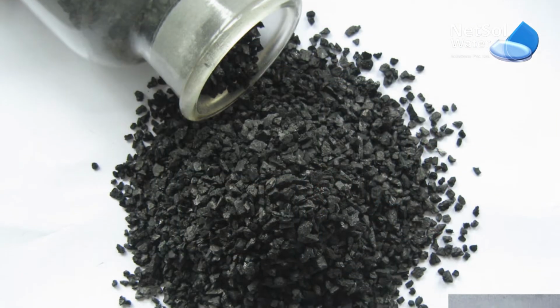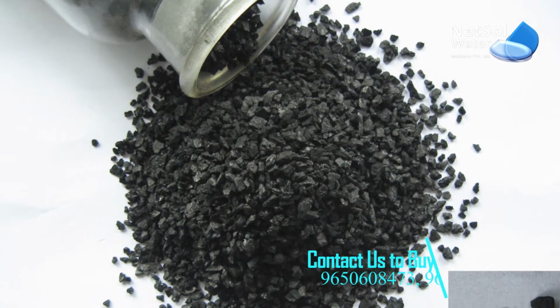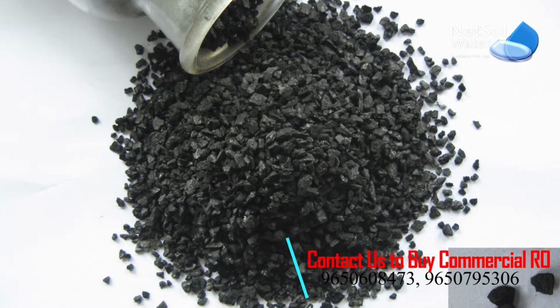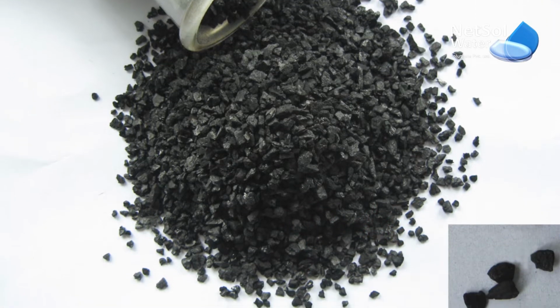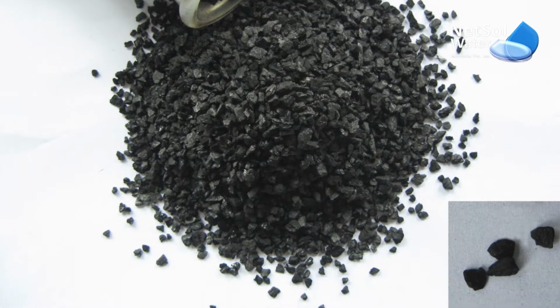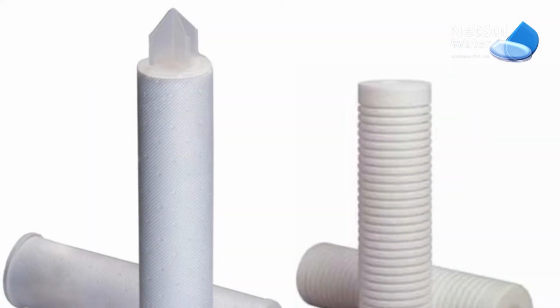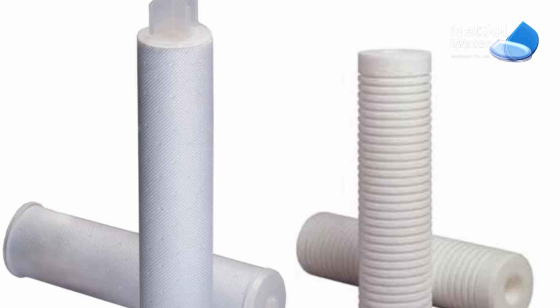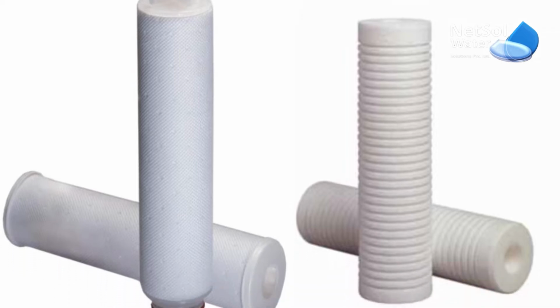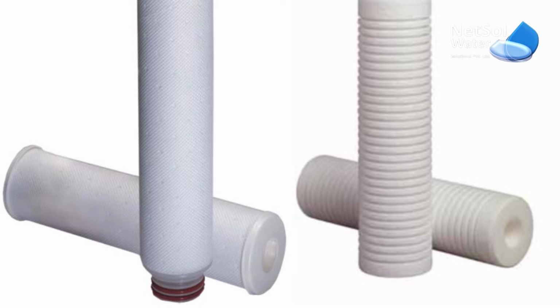The first method is the use of granular activated carbon or GAC. It removes free chlorine and organic debris in an automatic backwashing machine. Second is to install 5 micron absolute rated depth filters to reduce particle and fouling index.